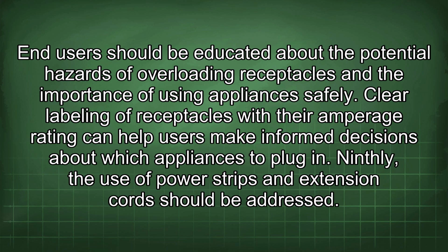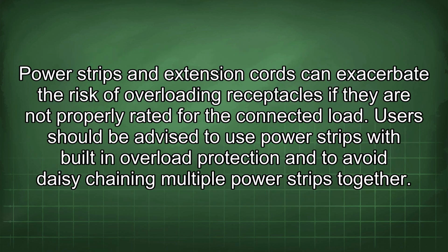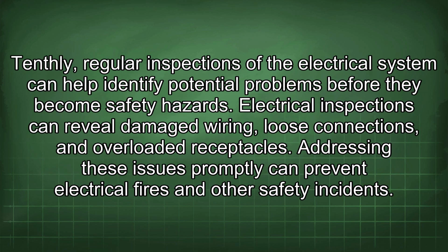Ninthly, the use of power strips and extension cords should be addressed. Power strips and extension cords can exacerbate the risk of overloading receptacles if they are not properly rated for the connected load. Users should be advised to use power strips with built-in overload protection and to avoid daisy chaining multiple power strips together. Tenthly, regular inspections of the electrical system can help identify potential problems before they become safety hazards. Electrical inspections can reveal damaged wiring, loose connections, and overloaded receptacles. Addressing these issues promptly can prevent electrical fires and other safety incidents.